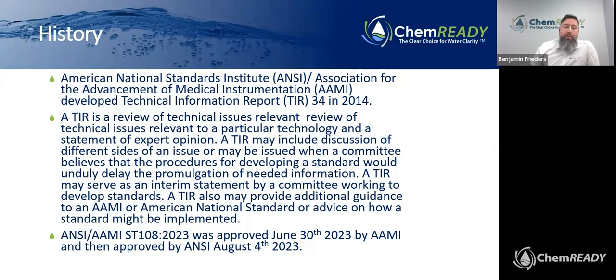AAMI ST108 came from this TIR 34. It was approved by AAMI on June 30th of last year, and it was finally approved by ANSI on August 4th. This webinar is celebrating the 1-year anniversary of the standard being published and all the implications that it will have for your facilities.